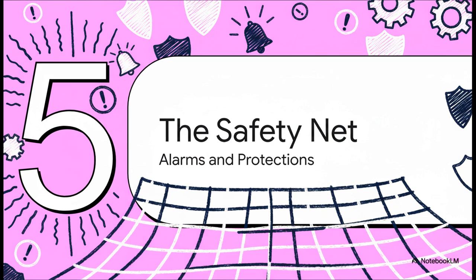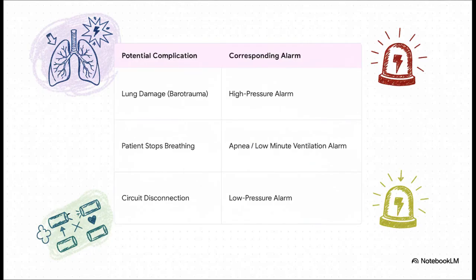Okay, so with all these critical settings and potential risks, you can imagine things can sometimes go wrong. That's where the ventilator's safety net comes in. The alarms on these machines aren't just annoying beeps, they are a patient's lifeline. Check this out. Each alarm is tied to a specific danger. If the pressure in the system suddenly spikes, which could be a sign of lung damage, bam, the high-pressure alarm goes off. If the patient themselves stops breathing, an apnea alarm sounds. If the tubing somehow gets disconnected, a low-pressure alarm tells the team immediately. It's a vigilant 24/7 guardian.